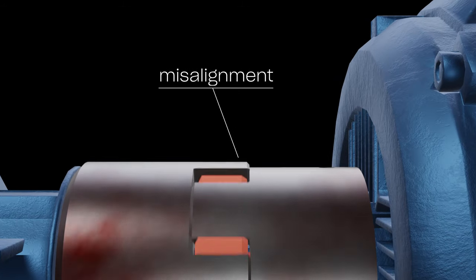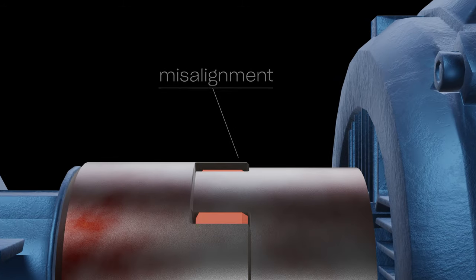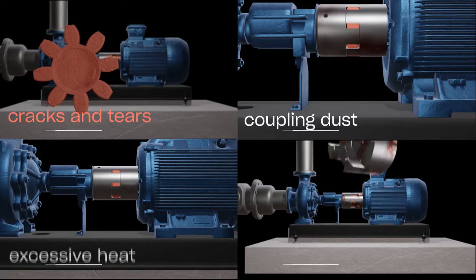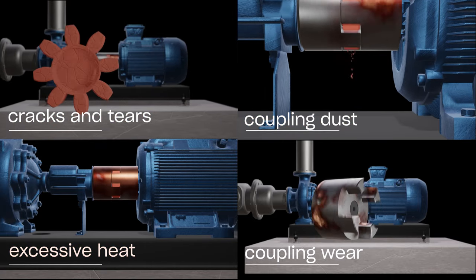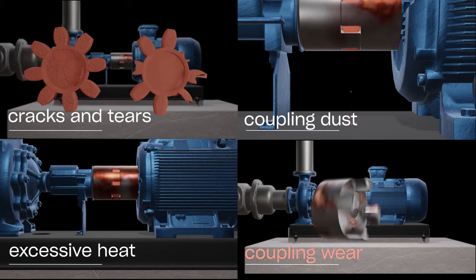Symptoms of misalignment to look for in the couplings include cracks or tears, coupling dust, changing of color due to excessive heat, and wear on coupling teeth.